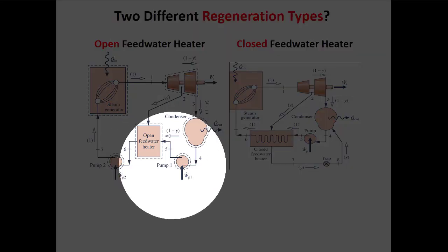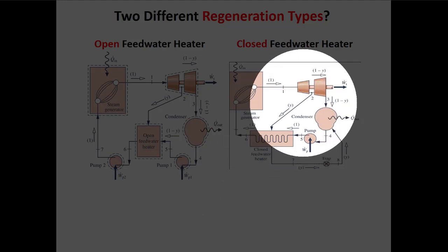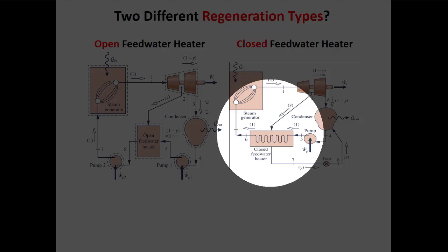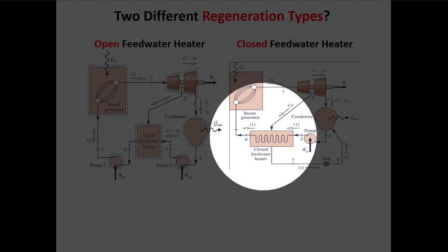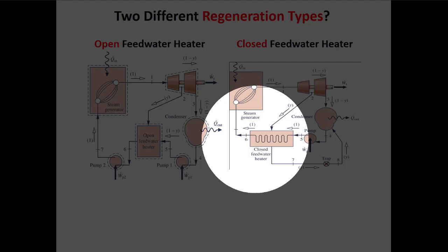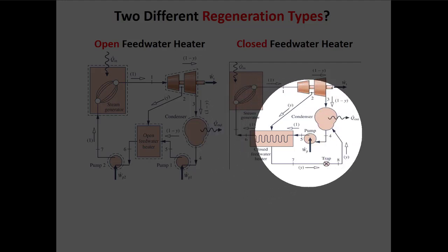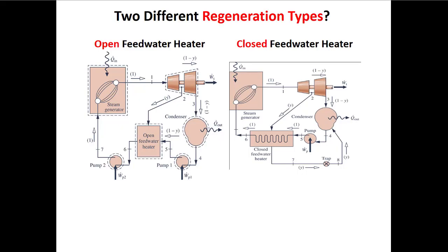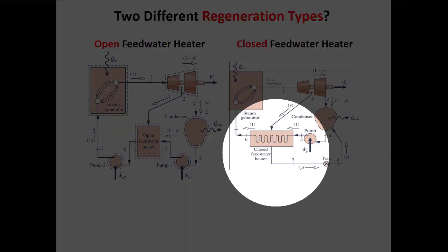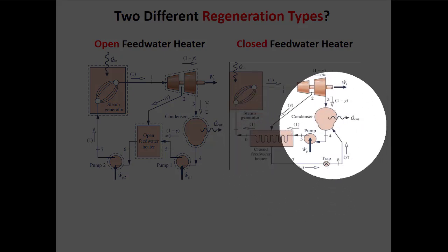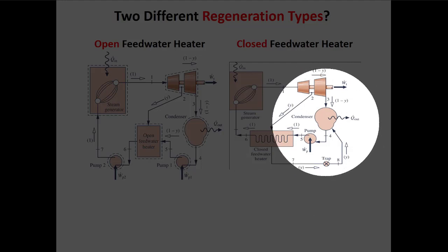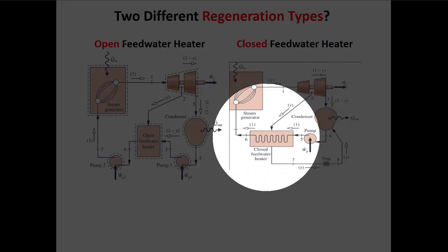An alternative is the closed feed water heater. Here, the higher-pressure, higher-enthalpy fluid runs through a shell-and-tube heat exchanger — the hot fluid runs through the shell and the cold condensed fluid runs through the tube. Heat is transferred from the hot side to the cold side, but they never physically mix. The hot mass flow gets cooled in the closed feed water heater, then runs back to the condenser where it also condenses, and the condensed fluid is preheated as it runs through the feed water heater.